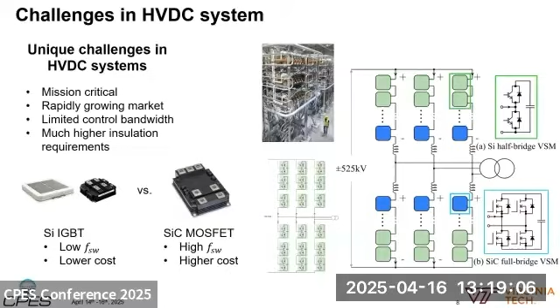The idea here is to replace a portion, for example 5 to 10%, of the silicon-based IGBT half-bridge submodules with silicon carbide MOSFET-based full-bridge submodules, shown on the right-hand side as the blue box. This modification enables the MMC to have a higher switching frequency and push the control bandwidth even further.